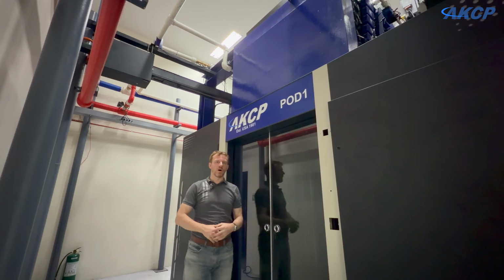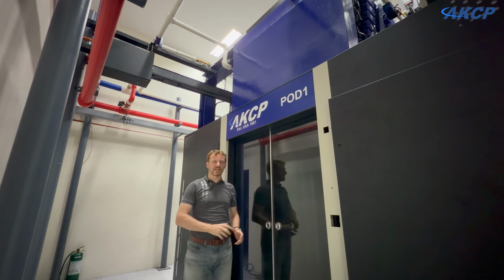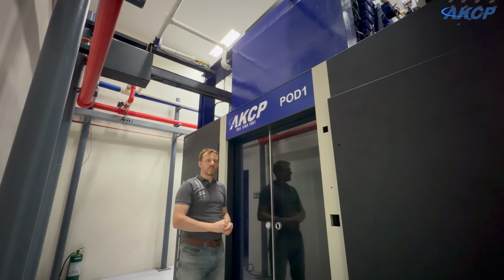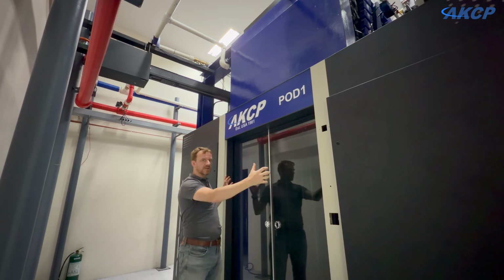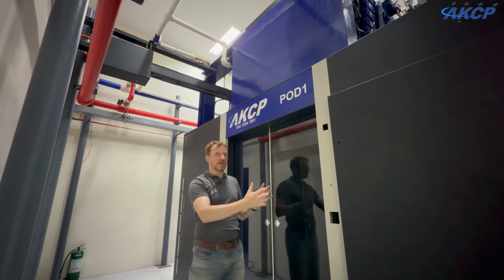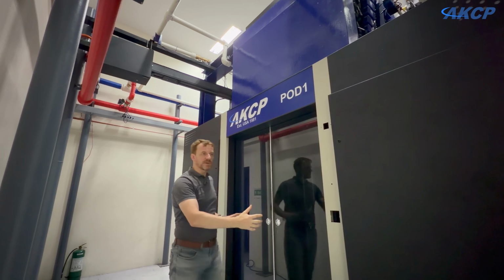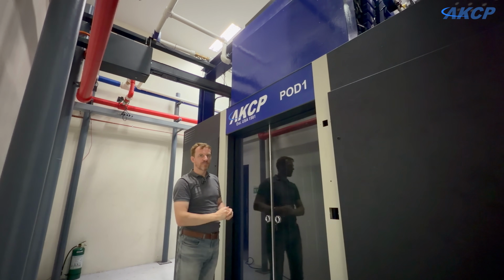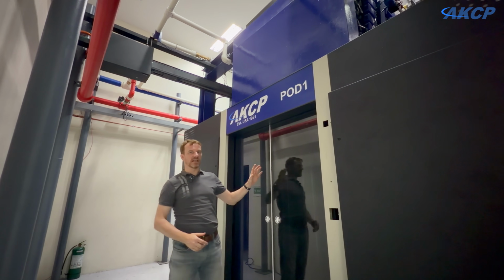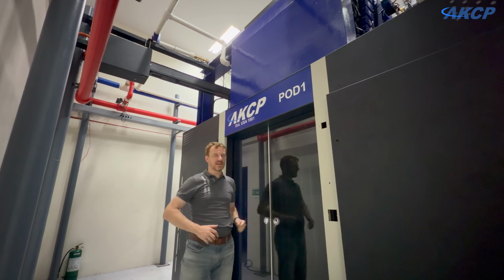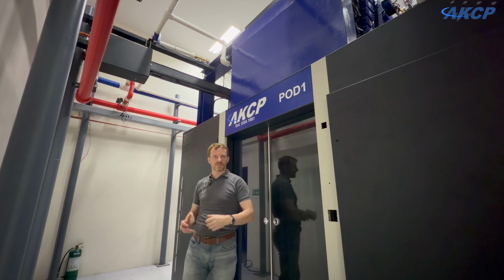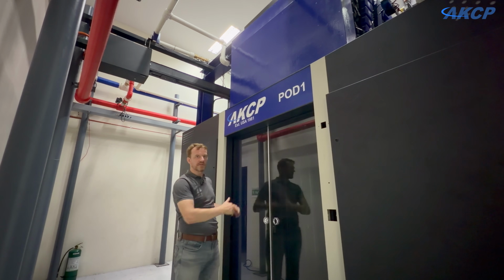So this is pod 1 of our test data center. This is our hot aisle containment, meaning that all of the hot air that is being generated by the racks is being trapped in the middle of here. That hot air then circulates through our air handling units and we blow cold air out into the room. So the room is cold and the hot air is contained.